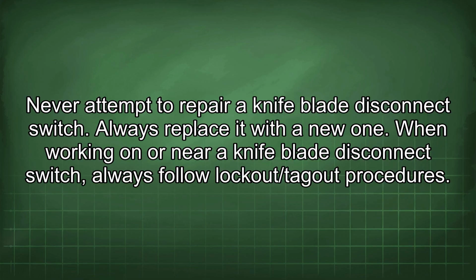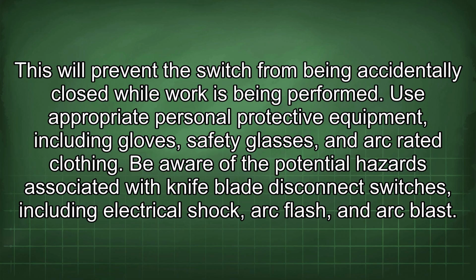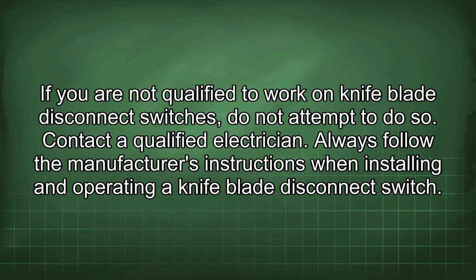When working on or near a knife blade disconnect switch, always follow lockout/tagout procedures. This will prevent the switch from being accidentally closed while work is being performed. Use appropriate personal protective equipment, including gloves, safety glasses, and arc-rated clothing. Be aware of the potential hazards associated with knife blade disconnect switches, including electrical shock, arc flash, and arc blast. If you are not qualified to work on knife blade disconnect switches, do not attempt to do so. Contact a qualified electrician. Always follow the manufacturer's instructions when installing and operating a knife blade disconnect switch.